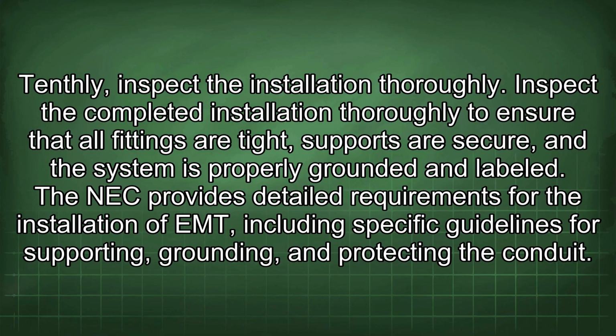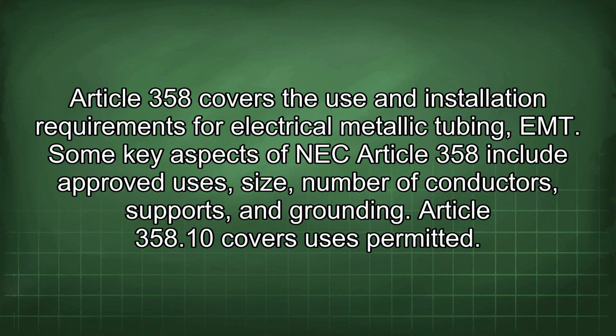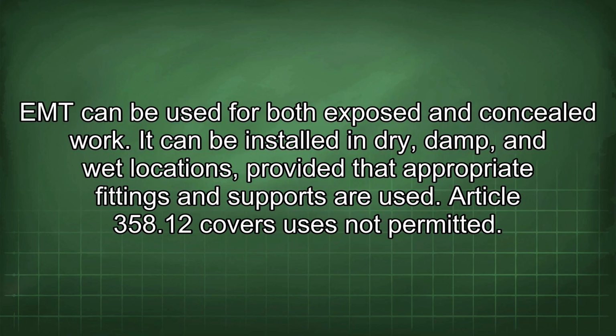protecting the conduit. Article 358 covers the use and installation requirements for electrical metallic tubing, EMT. Some key aspects of NEC Article 358 include approved uses, size, number of conductors, supports, and grounding. Article 358.10 covers uses permitted. EMT can be used for both exposed and concealed work. It can be installed in dry, damp, and wet locations, provided that appropriate fittings and supports are used.